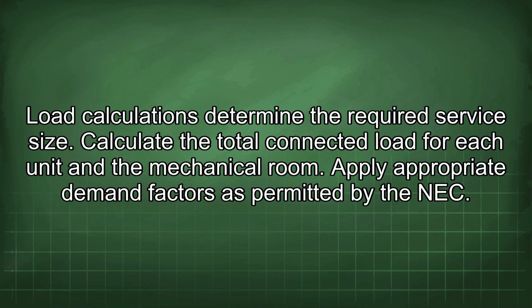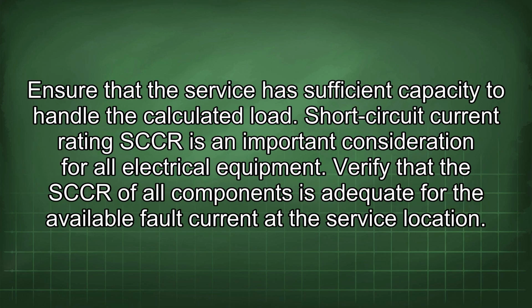Load calculations determine the required service size. Calculate the total connected load for each unit and the mechanical room. Apply appropriate demand factors as permitted by the NEC. Ensure that the service has sufficient capacity to handle the calculated load.